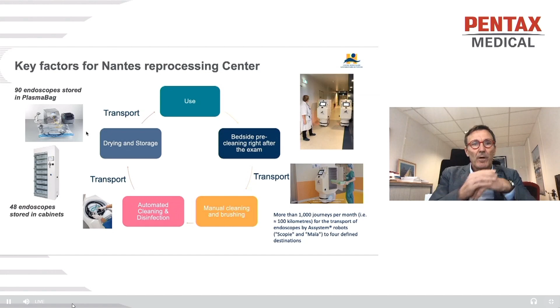Then we need to store endoscopes with the PlasmaBAG. So, endoscope drying and storage. At the end of the washing and disinfecting procedure, there is the possibility to use a system that dries the channel of the endoscopes completely and protects it from the development of biofilm. So we can see in this photo the device, the PlasmaTYPHOON, an automatic device to quickly dry the endoscope channels after disinfection, as an automatic washer disinfector with a drying cycle of up to 1-2 minutes with medical air. Very easy to use.